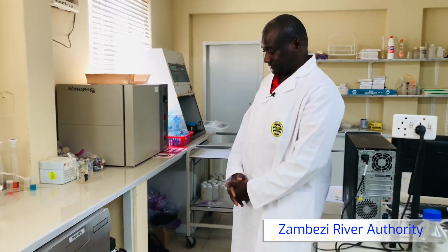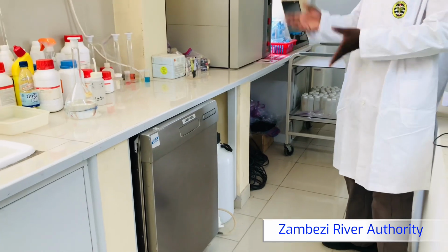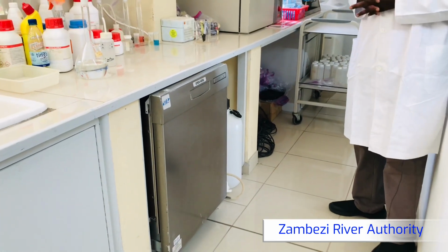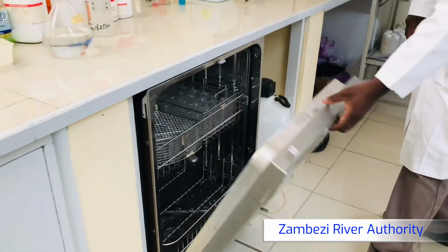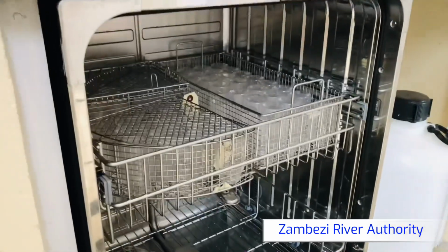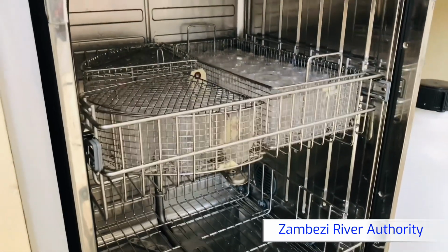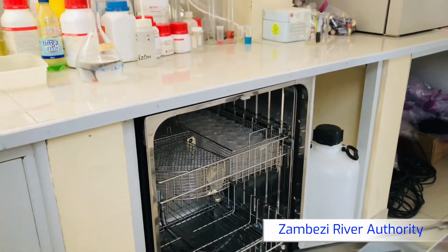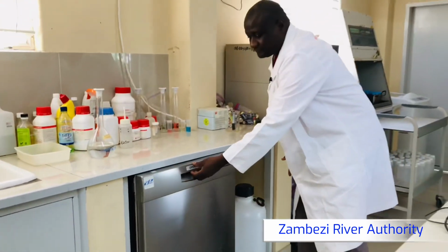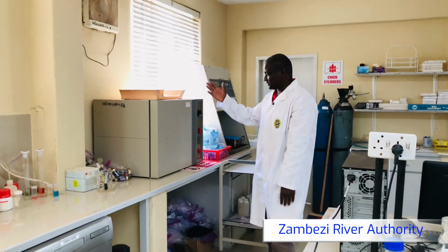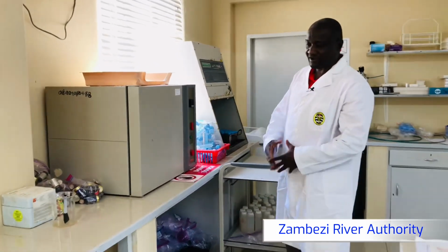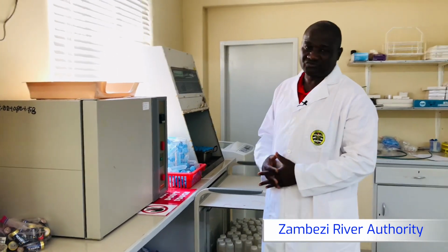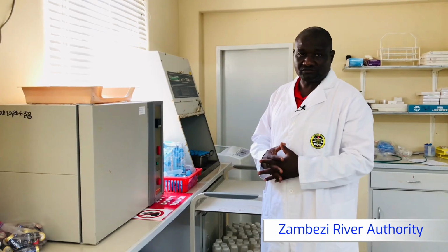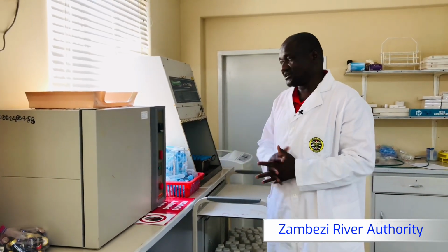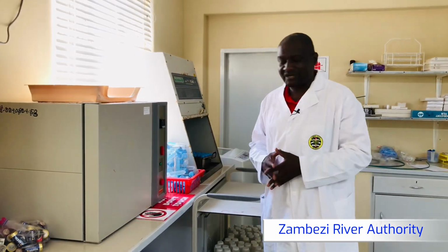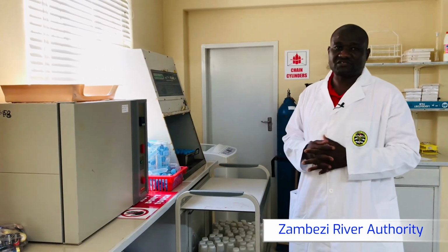Okay. So what we have here is a glassware washer. Instead of doing manual washing of our glassware, we acquired this equipment. It's basically similar to a washing machine, but it's meant for washing labware. So all the dirty bottles, sampling bottles are washed in this glassware washer. Then what we have here is an oven. We use it for drying our glassware, as well as for dry sterilization, say for bacteriological sampling bottles. It's usually done at about 160 degrees Celsius for at least 30 minutes.